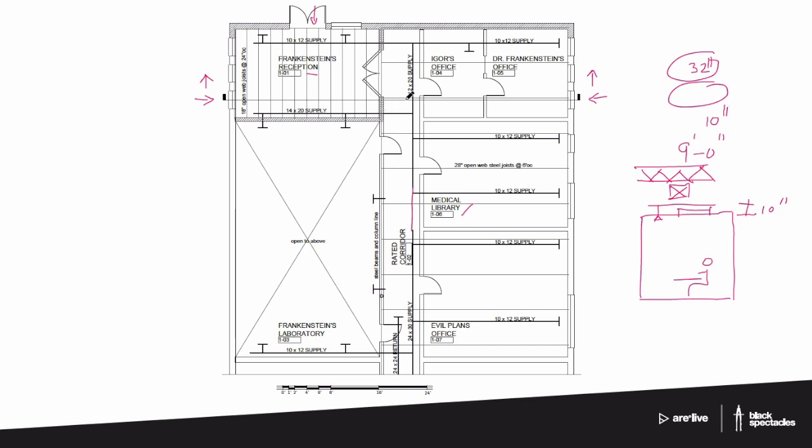So we look here, our section cut goes right across there, and there's our 12 by 20 supply duct. So we can do that. Obviously, you can always use the shorter number. So that would make that a 12-inch. Is that right? That is not right. How do I know, Mike? That's not right? Well, because that happens to be what it is right where I do the section cut, but that's not the biggest duct that has to be accommodated.